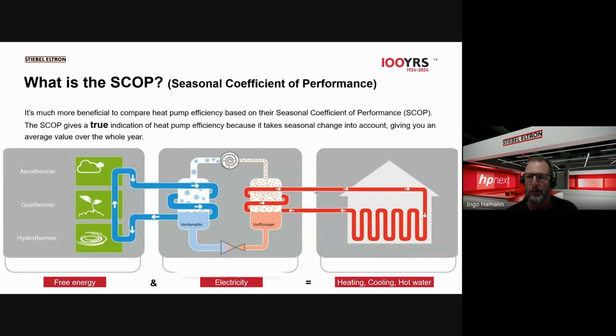So the trick is now to build a system which is able, especially in air source heat pumps, to cope with the different environmental temperatures, from -20 or even -25 up to 40, 46 degrees, like in the Kalahari. You have to look at the overall picture for the whole year. There's a lot of changes, measured in laboratories or in live measurements, and then put together as an SCOP. So basically, what have you put into your heat pump system over the whole year, including the circulation pumps, the power for the controller, everything, and what could you gain from the environment, and what was the output? That is then your SCOP.